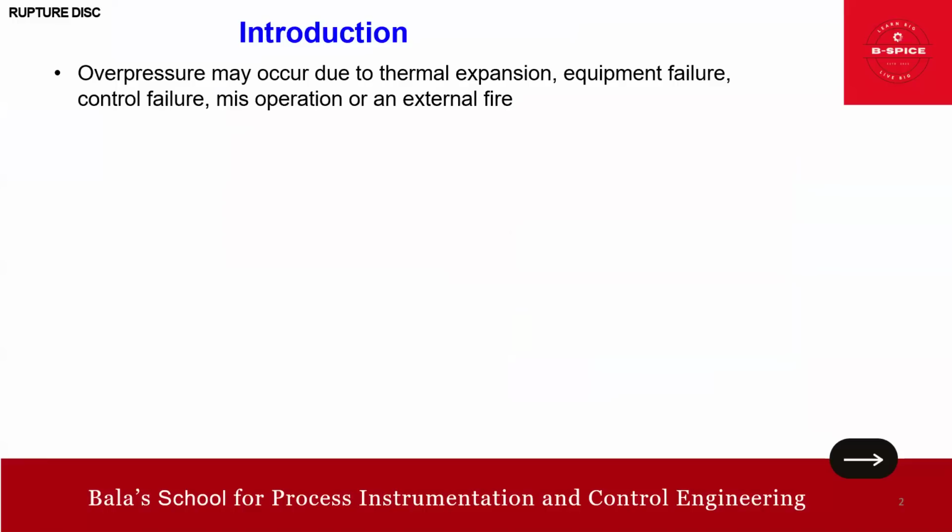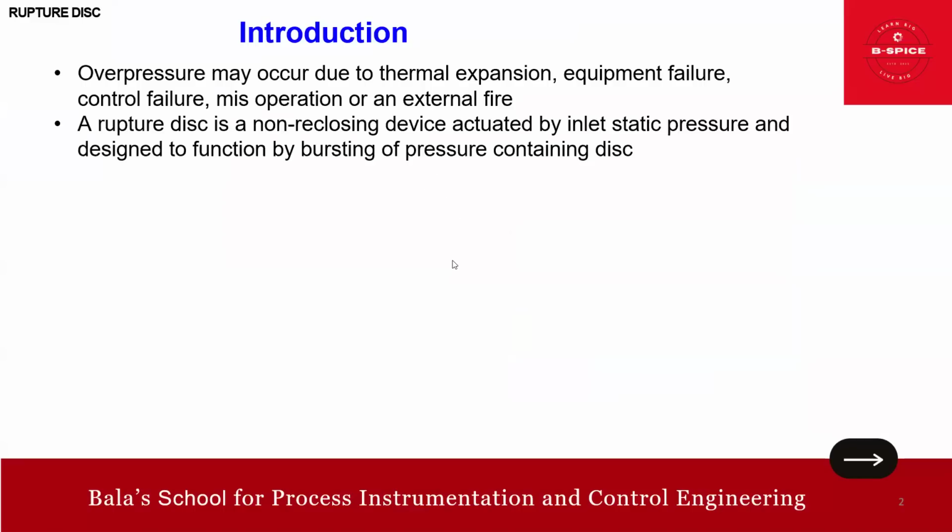Friends, overpressure may occur due to what? Thermal expansion, equipment failure, control aspect failure, misoperation, or external fire. I hope you agree, right? So a rupture disk is a non-reclosing device actuated by inlet static pressure and designed to function by bursting of a pressure containing disk. That's it.